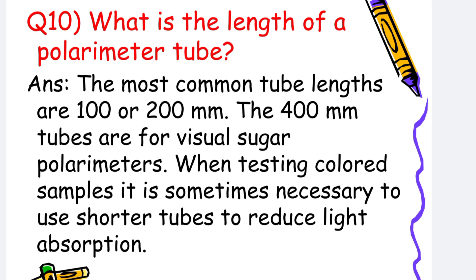What is the length of a polarimeter tube? The most common tube lengths are 100 to 200 mm. The 400 mm tubes are for visual sugar polarimeters. When testing colored samples, it is sometimes necessary to use a shorter tube to reduce light absorption.